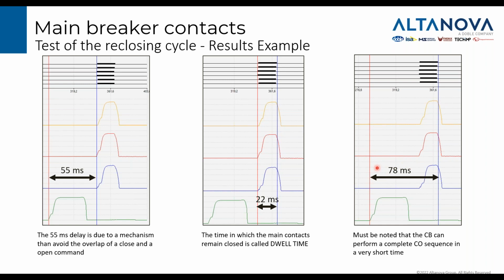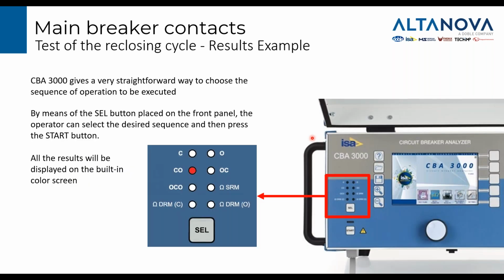This is the proof. These are real results that the circuit breaker can perform a complete close-open sequence in a very short time. In this example, it is 78 milliseconds. With CBA 3000, it's possible to choose this sequence in a very easy way. There is a selection button that will give you the possibility to choose if you want to do just a close operation, an open operation, or a combination of the two: close open, open close, or open close open. The results will in the end be displayed on the color screen here for the interpretation of the results.